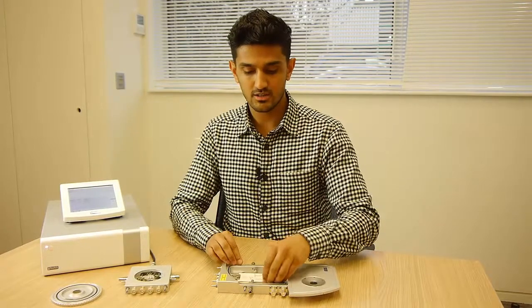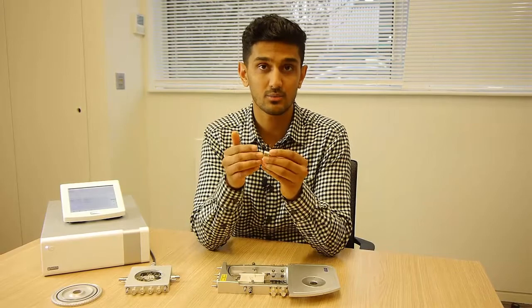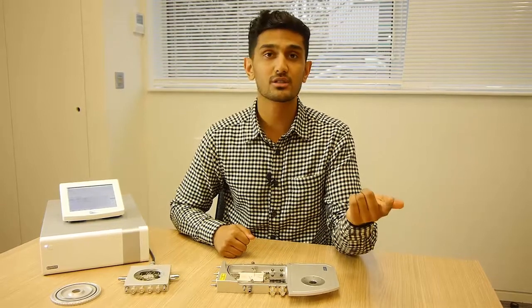Your stage is going to come with these probes that are made from tungsten tipped with gold. What they allow you to do is measure the electrical characteristics of your sample. For that reason they're really popular in thin film research applications, 2D materials such as graphene and black phosphorus studies, and also if you want to measure any small electronics in a controlled environment.